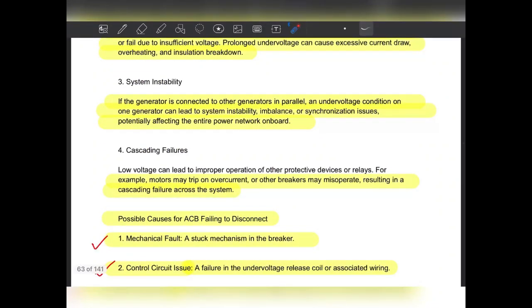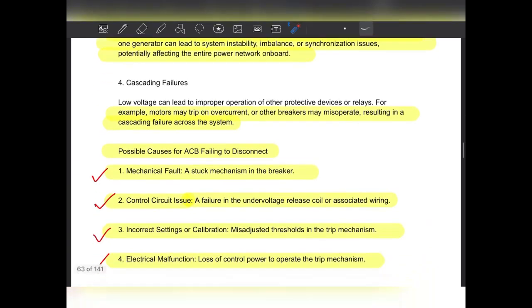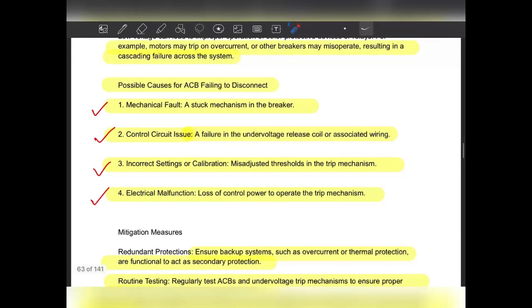Okay, if the generator is connected to another generator in parallel under an under voltage condition, one generator will lead to system instability. Okay, and what are the possible causes for the ACB failing to disconnect? Let's suppose the ACB does not disconnect, what are the reasons? Maybe the surveyor will ask you also.